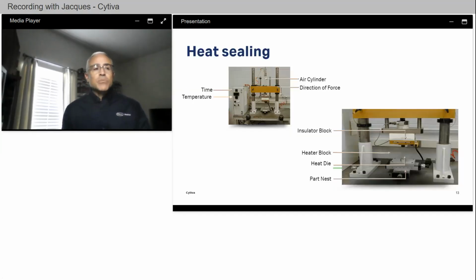Now, the first method we will discuss is heat sealing. In most cases, this will be the recommended membrane sealing method. Heat sealing equipment may vary from model to model, and most models share these specific four features. Number one, controls that monitor the time, temperature, and pressure of the equipment, a heater block and a heater block insulator assembly, a heated die that contacts the components during the heat sealing process, and a nest or part fixture that will hold the device housing and filter membrane components during the heat sealing process.